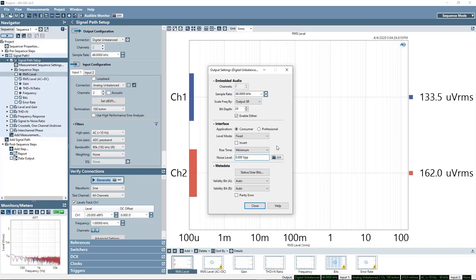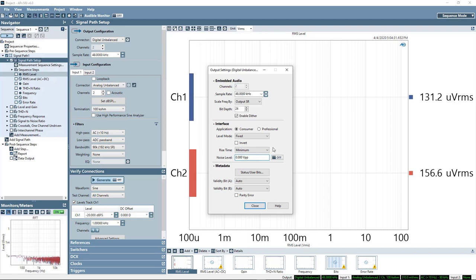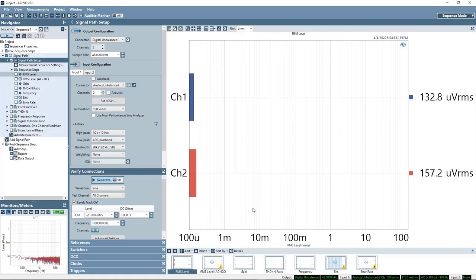We can also modulate the rise time of the physical interface and or add noise to it. We can also do tests where we look at the jitter tolerance of the device.